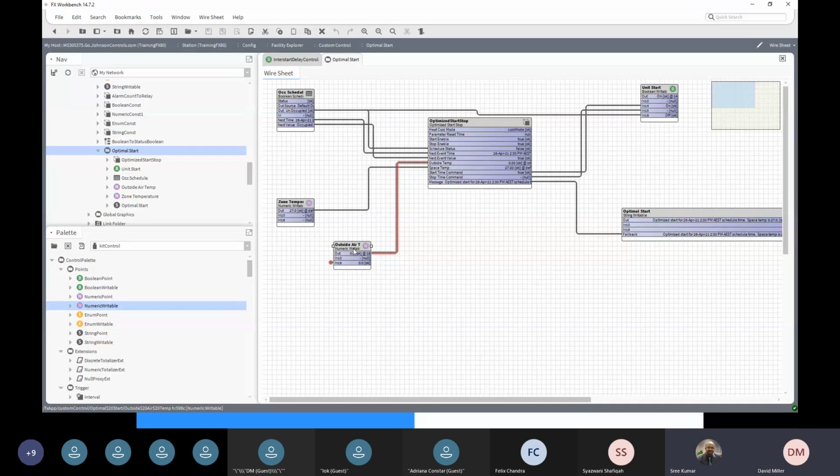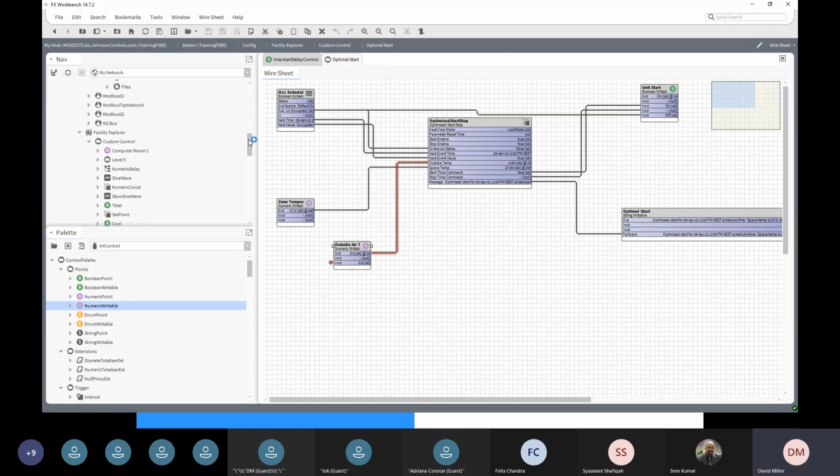Do we consume any license when we connect one FX80 to another, or is it considered a Fox point? That's right, it's a Fox point, so it's free. There's no limit between FX80s. The only time you use connections from a licensing point of view is when the FX server connects to an FX80.